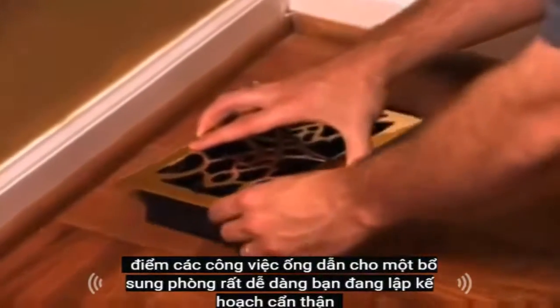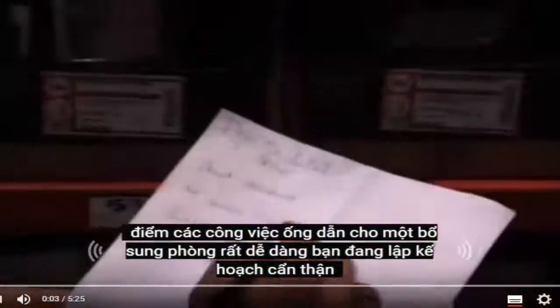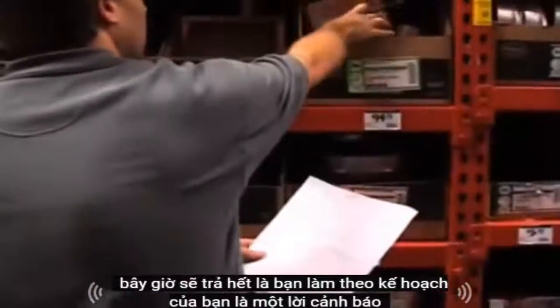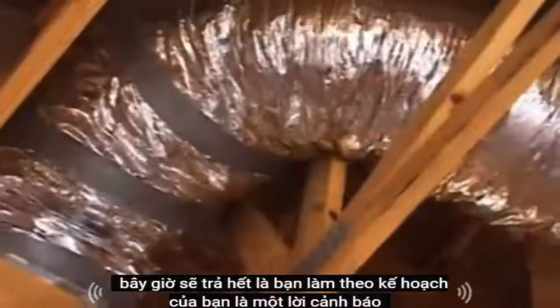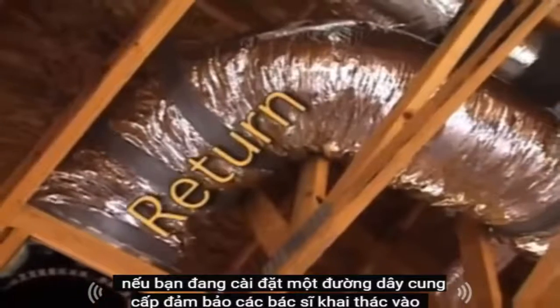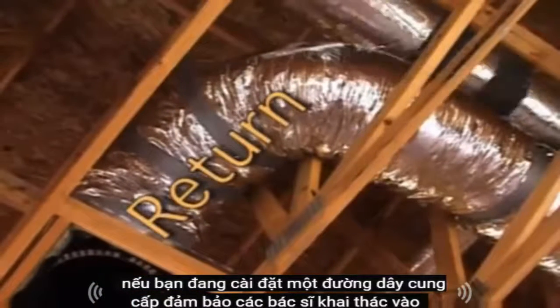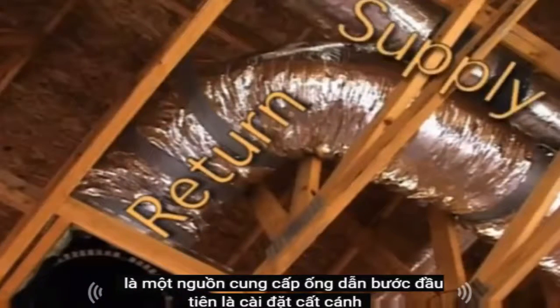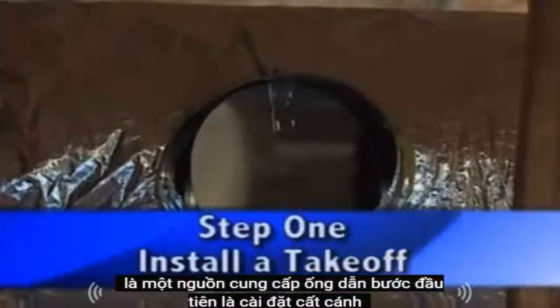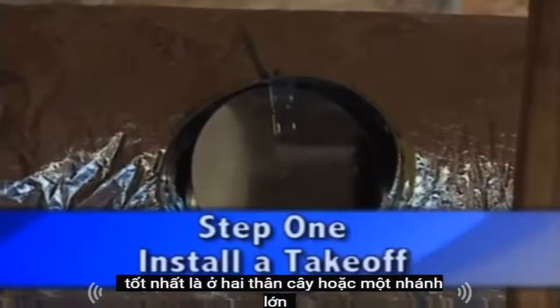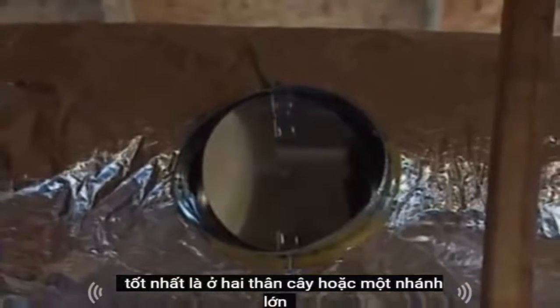Installing the ductwork for a room addition is easy. Your careful planning will now pay off as you follow your plan. A word of warning, if you're installing a supply line, make sure the duct you're tapping into is a supply duct. The first step is to install the takeoff, preferably on either the trunk or a large branch.